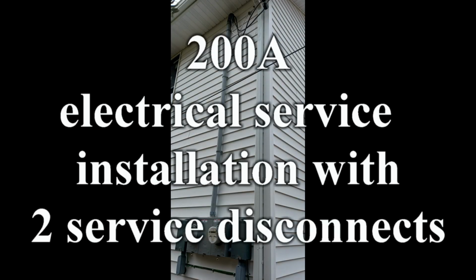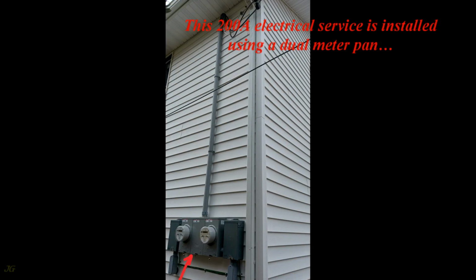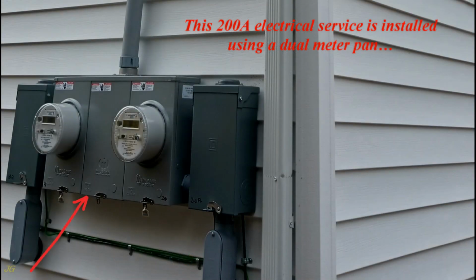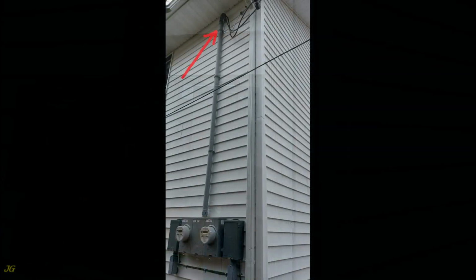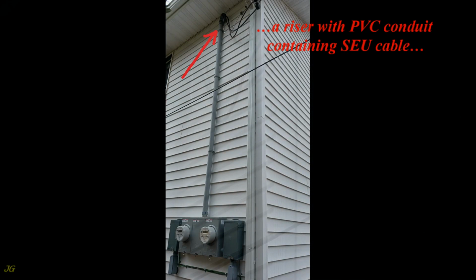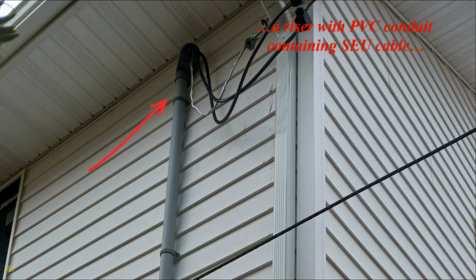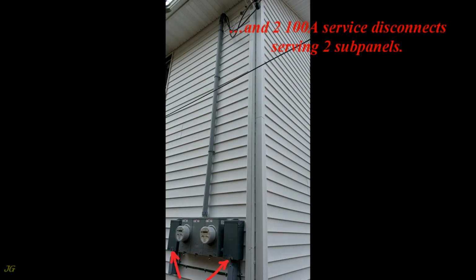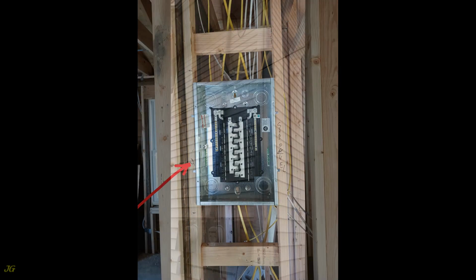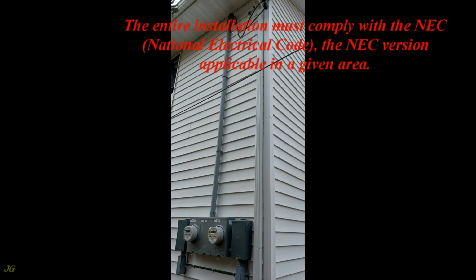200 amps electrical service installation with 2 service disconnects. This 200 amps electrical service is installed using a dual meter pan, a riser with PVC conduit containing SEU cable, and 2 100 amps service disconnects serving 2 subpanels. The entire installation must comply with the NEC, National Electrical Code, the NEC version applicable in a given area.